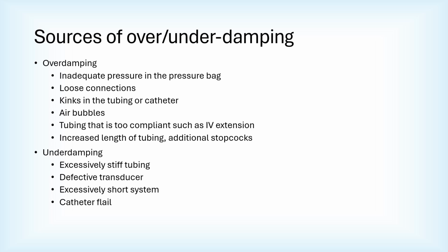Underdamping is much less common by design, but can be caused by things such as excessively stiff tubing, defective transducers, an excessively short system, or a catheter flailing in an artery.